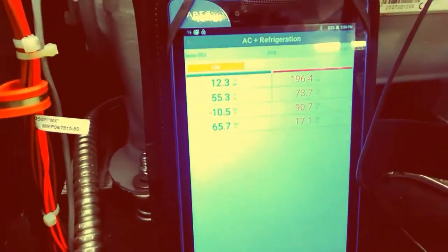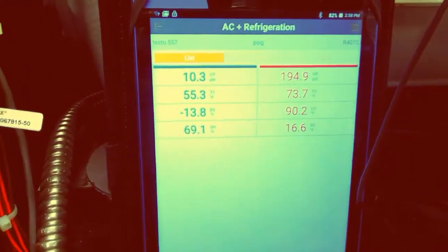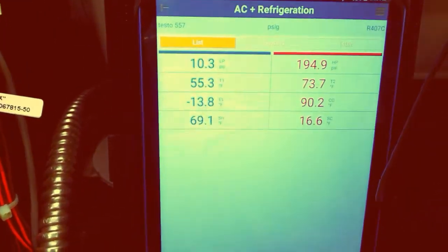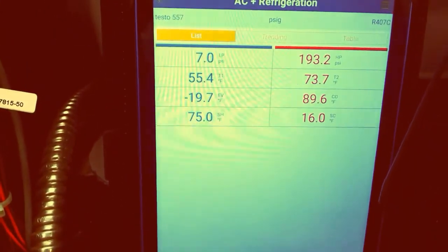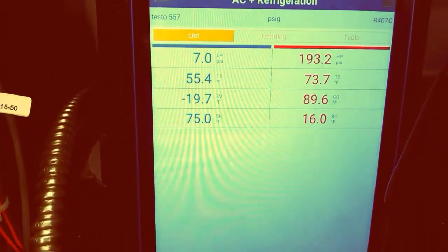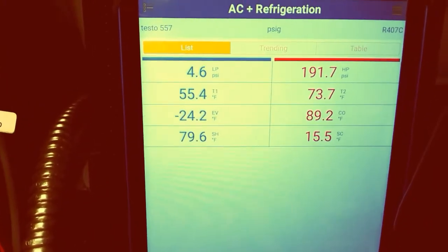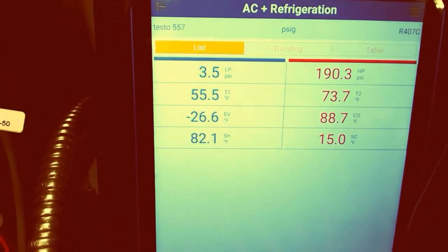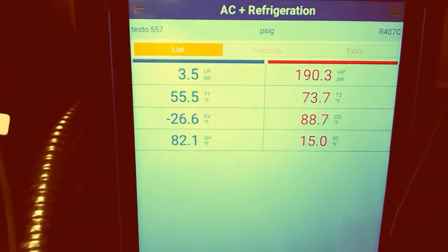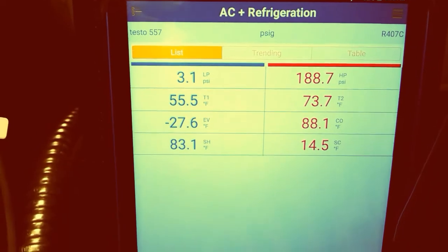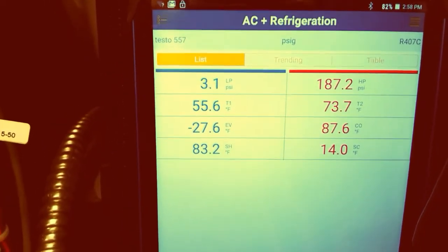You can see that the system is off right now by the pressures. We got 4.6 on the low side and 190 on the high side. That machine has pumped down on the off cycle.